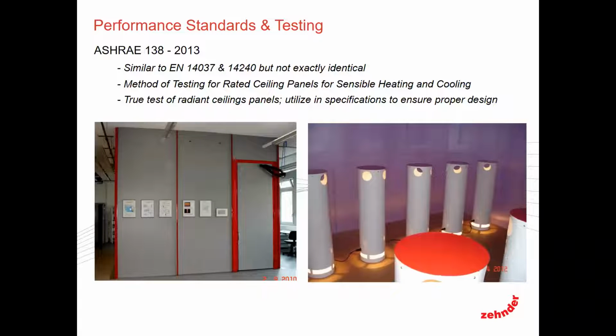In 2013, ASHRAE 6.5, the committee, we passed ASHRAE 138, which we took and used as the benchmark of the EN standards for cooling and heating, and we revised them and rewrote them to fit our market. So either or will work. They're both measurements for rating sensible only heating and cooling panels when you write your specifications, and you know as a designer that you're using the actual performance that's measured in a lab, third-party tested according to the standard.